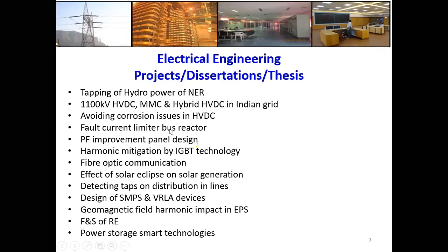Then fault current limiter bus reactor. We know that if more generation is coming onto any bus, and a fault happens, there will be huge fault current flowing through it, and sometimes that is not sustained. So there are some fault current limiter reactors that can be used for buses at some stations. You can go for this technology also, as very few applications exist so far.